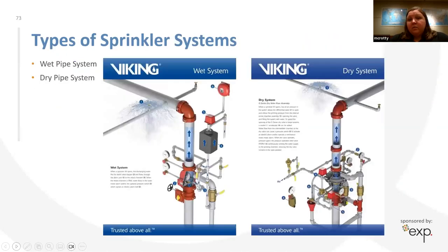There are many different types of sprinkler systems. The two most common are the wet pipe and dry pipe systems, which sound exactly like they're named. The wet pipe is full of water all the time - when the sprinkler pops and the link breaks, water comes out immediately. In the dry pipe system, the pipe is usually filled with compressed air, holding back the water closer to the riser. When the sprinkler pops, the loss of air pressure allows water to flow out. We use that mostly where we're concerned about freezing, so water in the pipe doesn't freeze and block it, preventing the system from working properly.